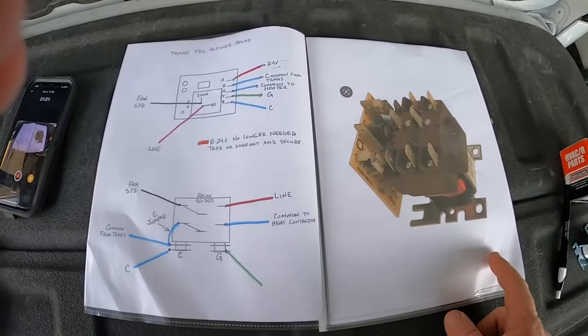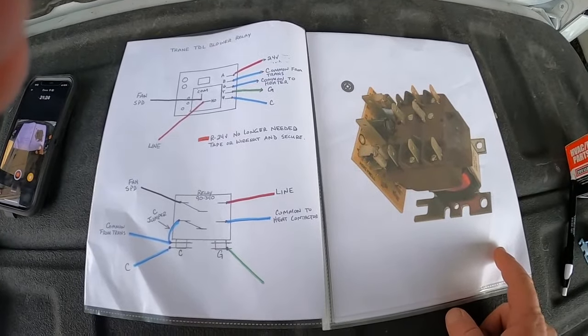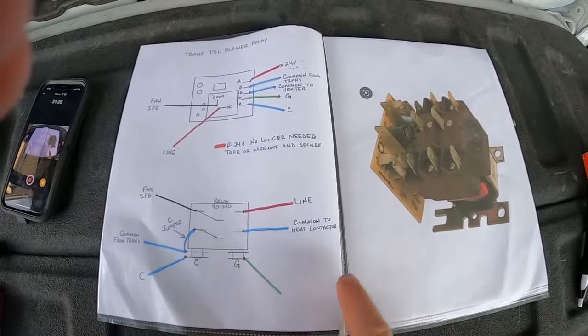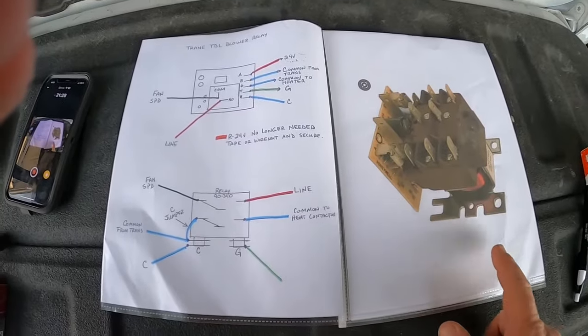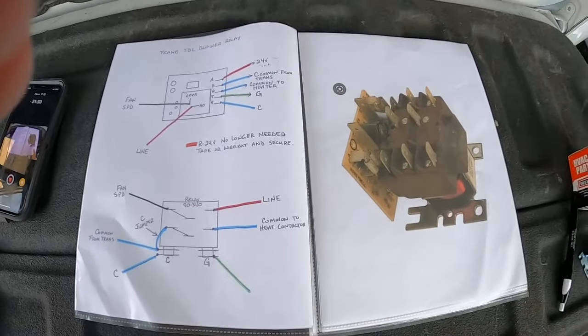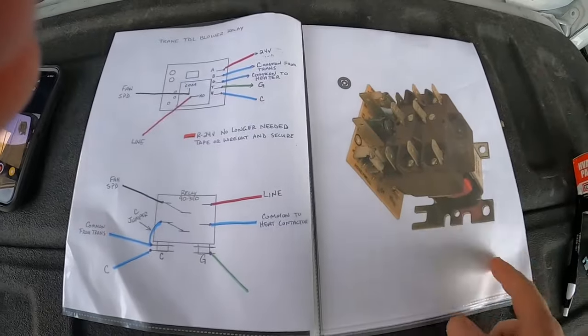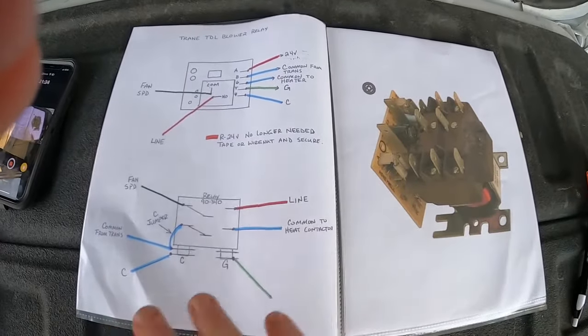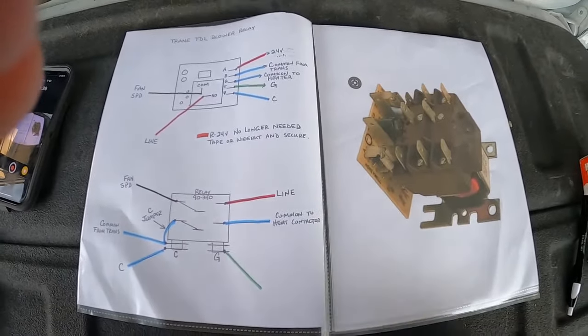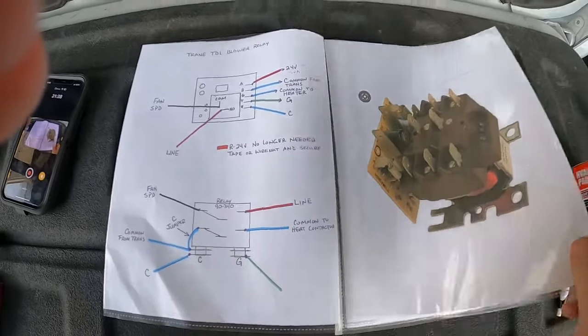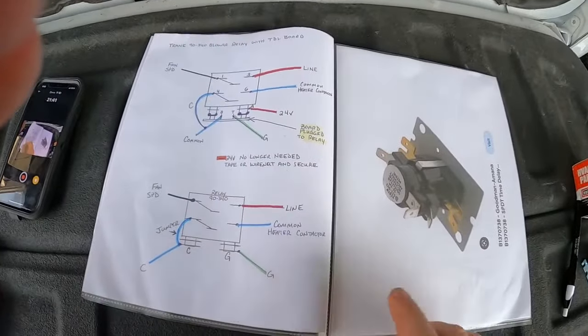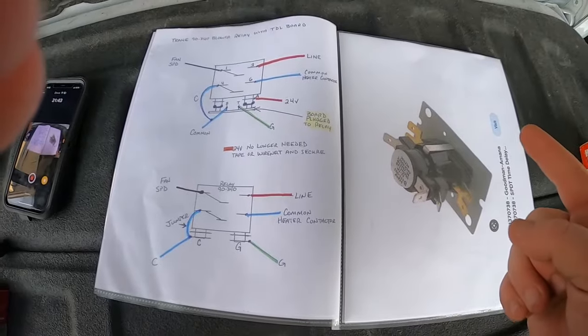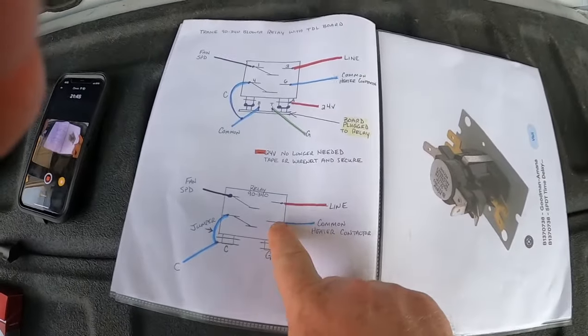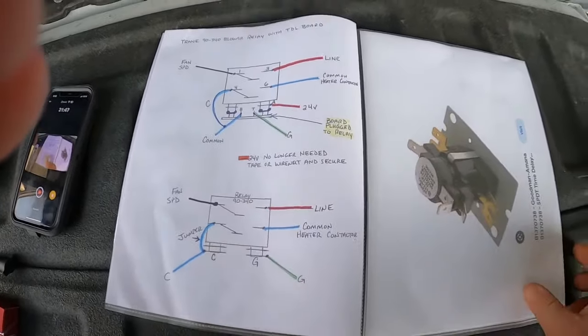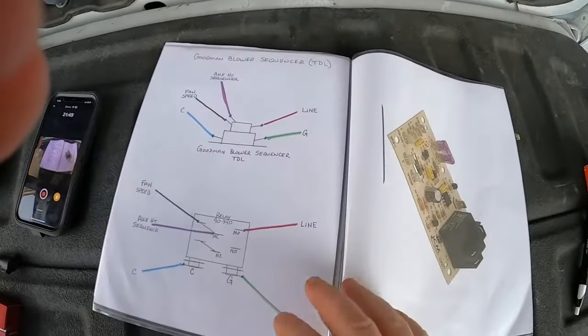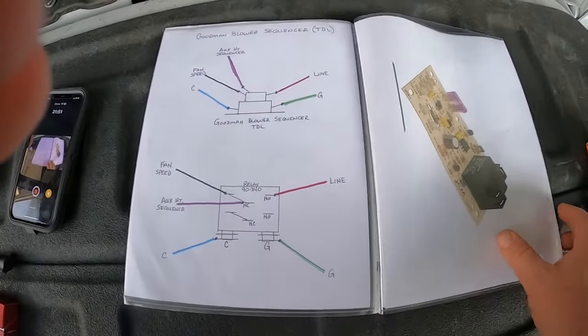You're going to energize your blower at that point. You want to make sure when the blower comes on, the only amp draw you have is for your blower motor. Then you want to de-energize, make sure when the blower shuts off, your amps go back to 0. Then you want to energize your heat strips, and you want to confirm that when your heat strips energize, you've got it wired up properly, that the blower is running. You don't have amps, you don't have heat strips running without airflow.